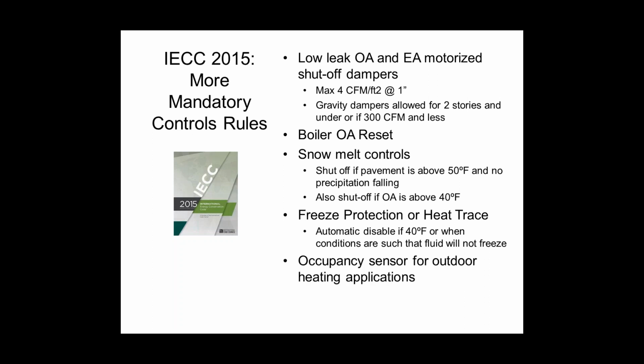If you decide you want to heat things outdoors, obviously you don't care about saving energy, but we're still going to try to force you to save a little bit. You have to use radiant heat. That is code required. I don't have it on the slides here because this is a controls topic, but you have to do it radiantly. That means tubing in the concrete or overhead infrared heaters. You cannot do any other method of heating. It has to be radiant-based heat. And from the control side of it, you have to have an occupancy sensor. So if you want to heat a beer garden with overhead infrared heaters and nobody's out there smoking and drinking, guess what? The sensor says nobody's there. We shut off the heater. Someone walks out there, we turn the heater back on.